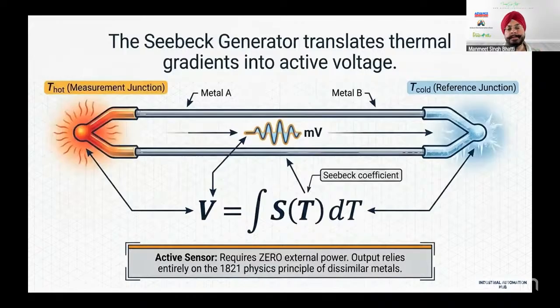Now, how it works basically, don't get into the formula part right now because the formula is meant for the calculations part. There is a principle by the name of Seebeck. The Seebeck principle says that if you have two dissimilar metals, metal A and metal B, both different ones, and if these two dissimilar metals are joined at one end, which is called a hot end. On the left side, you will see is a hot end, and on the right side, it's a cold reference junction or a reference junction.